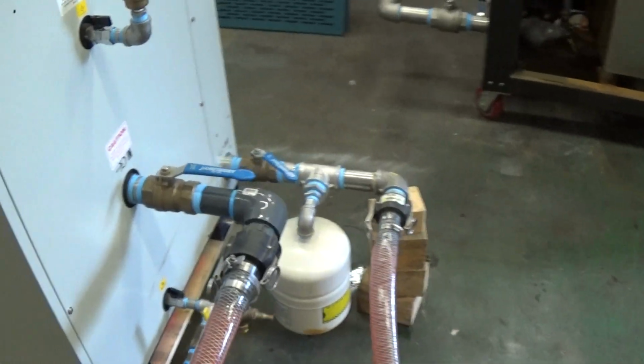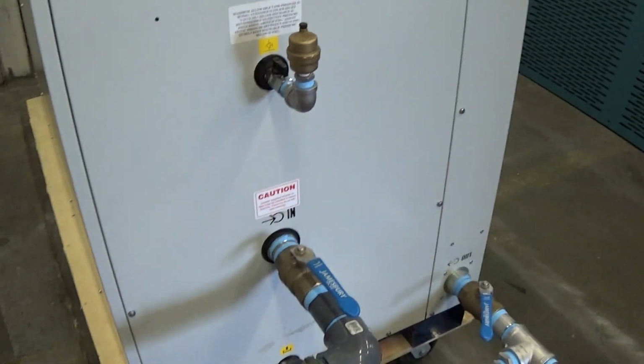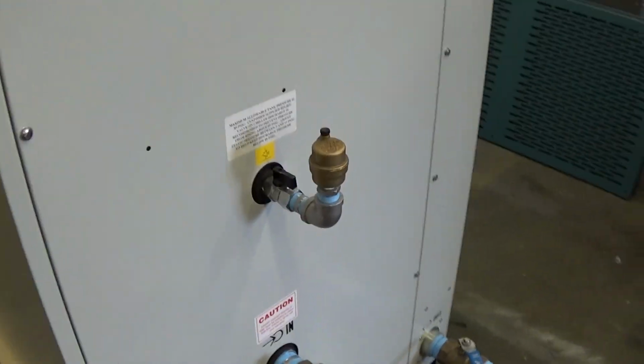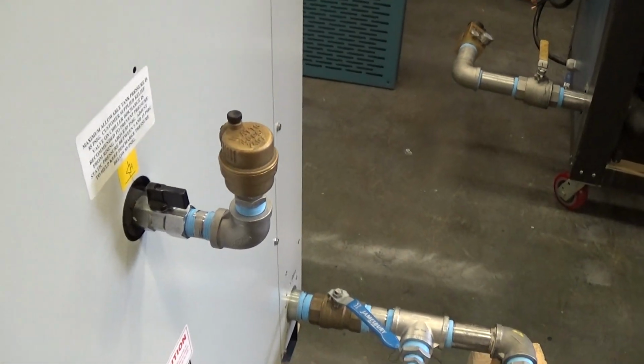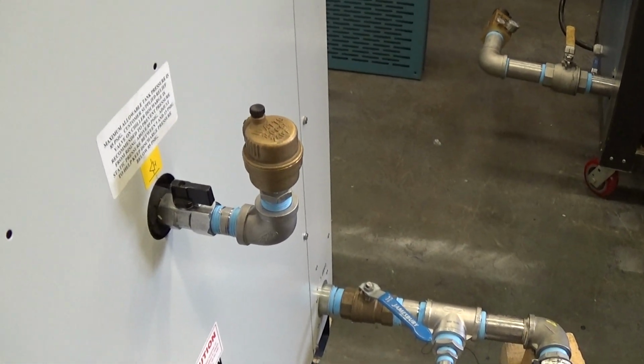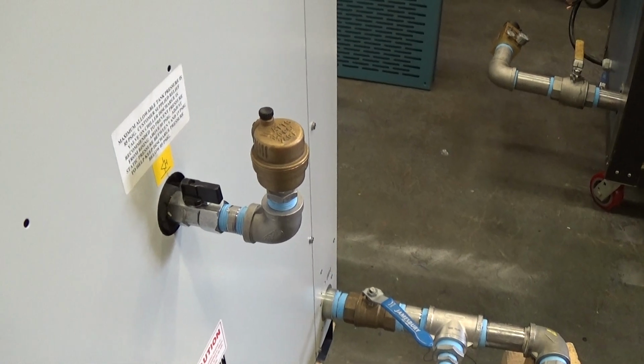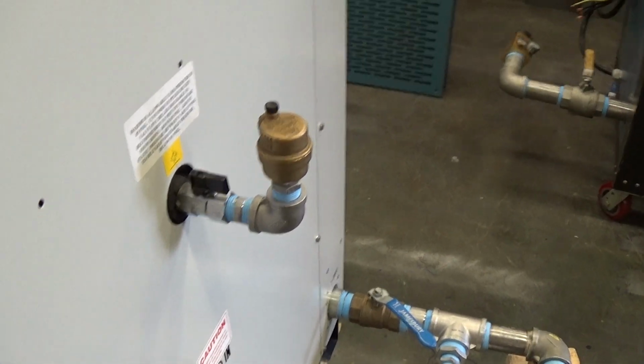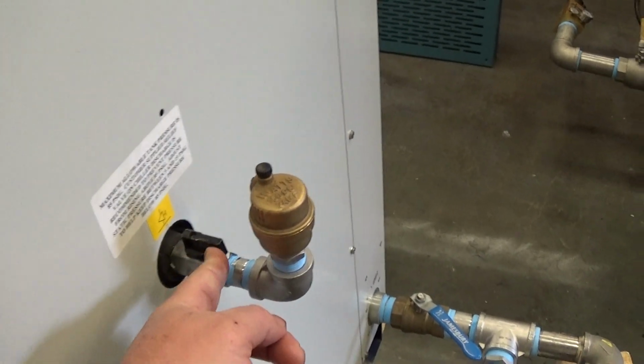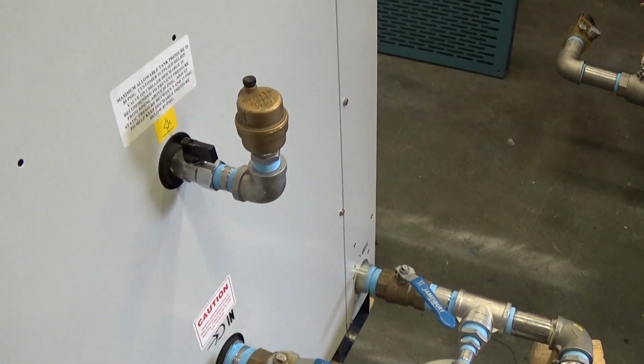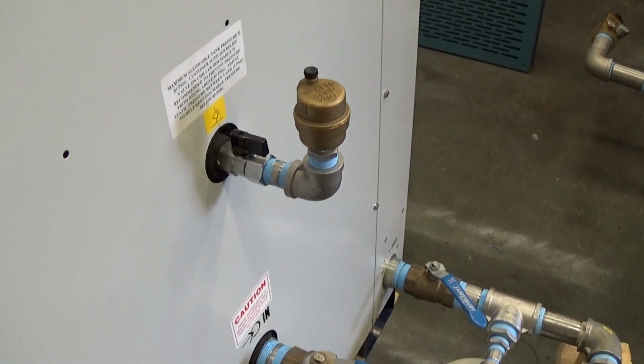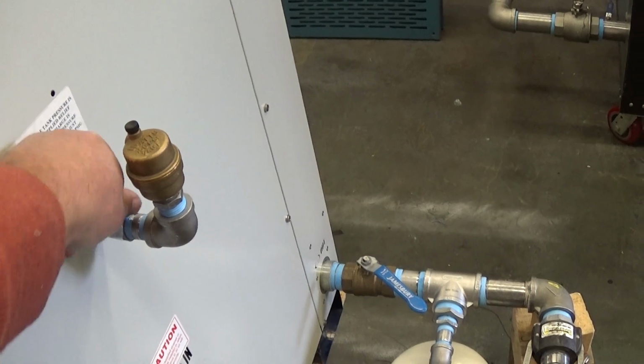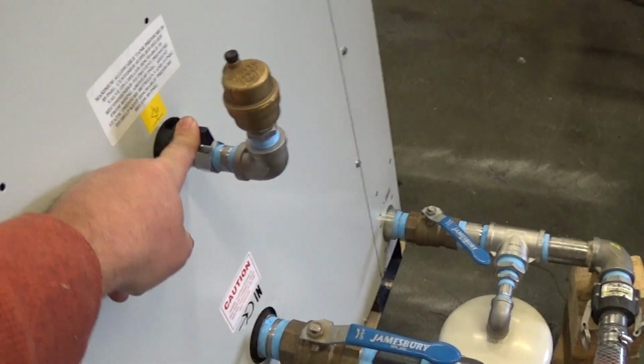As such, if you want, you can run the unit as a pressurized loop because the tank is sealed. You have a little air vent here. In normal operating conditions, for nearly all applications, you'll leave this open so it can vent off air. But if you do need to, for whatever reason, run a pressurized loop, you would close that valve here.